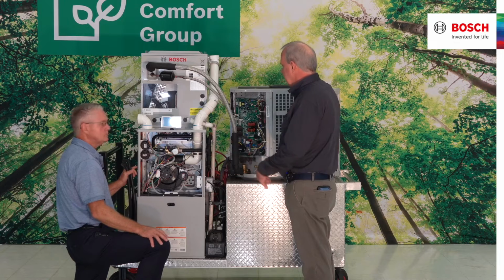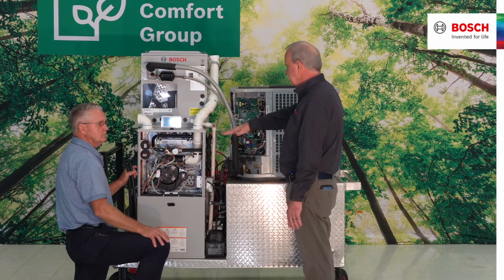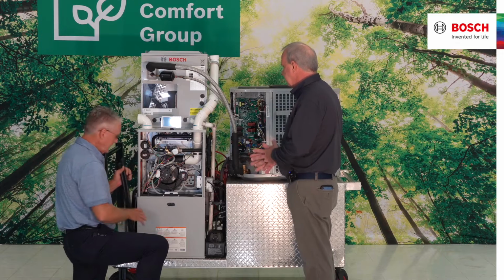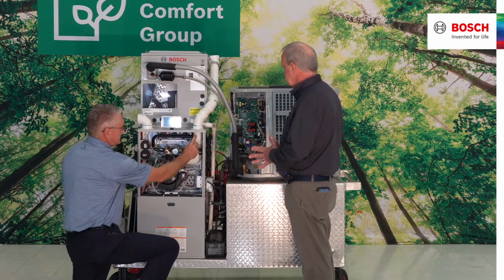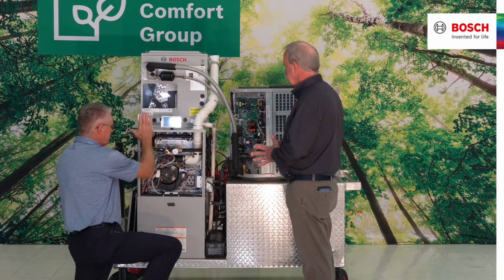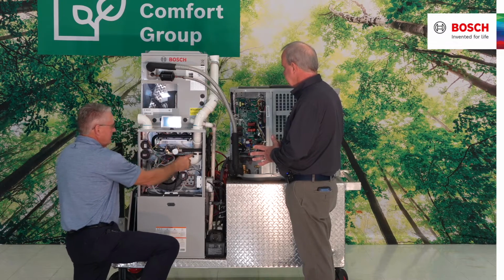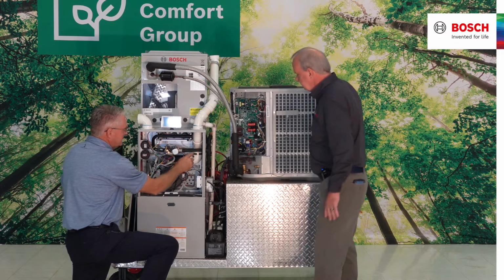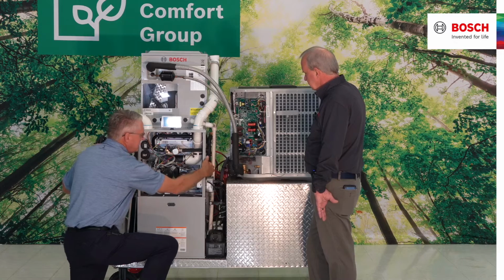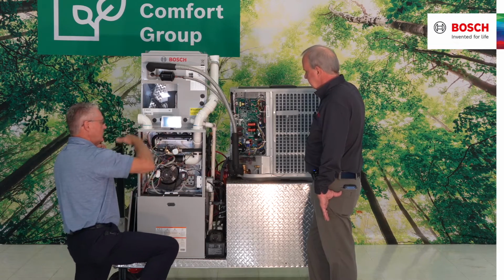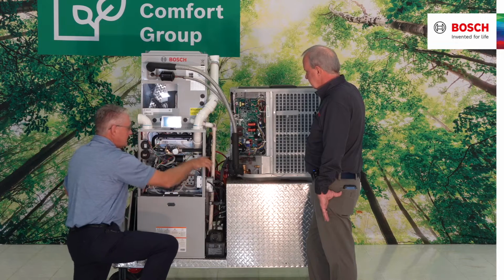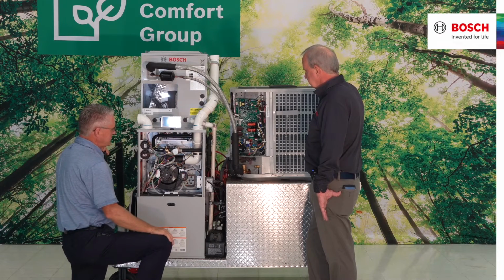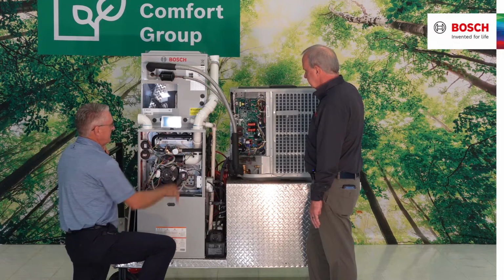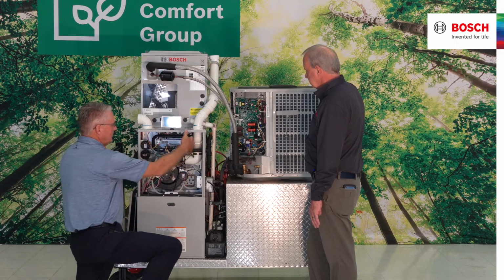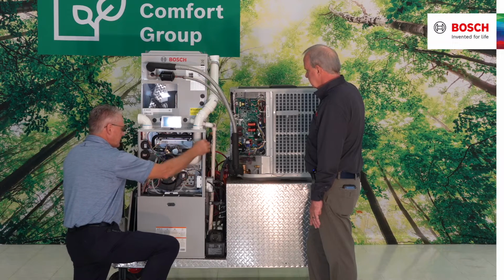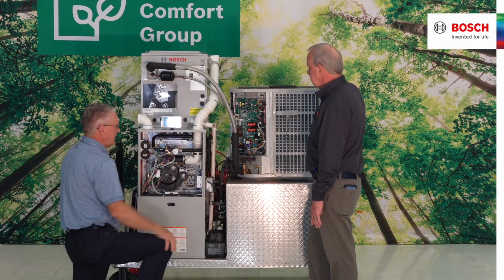In the horizontal left or horizontal right position, what are some of the changes that need to be made for those applications? Okay, so right now I have my vent. This is what we call the bad gas, the combustion gas, and this is the fresh air coming back in. This bad gas, I can take it out of the top or I can take it out of the side. So if I'm laying it down horizontally, I can basically vent it straight out and then go to my external exit point of the structure. That's one of the nice things about this: I have multiple places to bring the bad gas out of the cabinetry without having to cut any of the cabinetry itself.